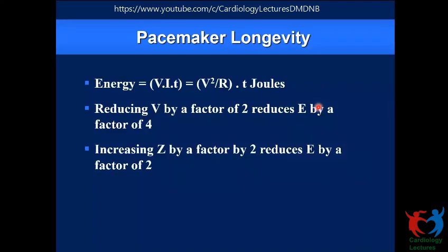Okay, so we touched upon this already when we were talking about programming the output to enhance or optimize the pacemaker longevity. Keep in mind that when we are programming the output or doubling the output, the energy outgo varies by the square of the voltage. But when the impedance increases 2 times, the energy outgo is halved. The battery would last significantly longer, but not exactly double, because there is other current drain from the pacemaker, as I described a little while ago.